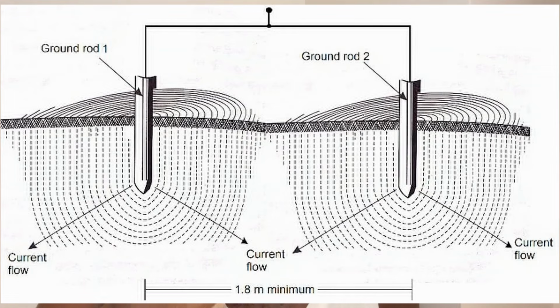Okay, if you're designing from scratch, I would say the earth rod should only be supplemental, bonded to the foundational earth itself, and installed in multiple locations if needed. Okay, if you didn't do the foundation earthing, that's not a problem, as long as you get the right quality of earth rod and you install them correctly, the right diameter, the right length, and spaced adequately, then you should be okay. But if you're starting from scratch, use the foundational earth system. It is much, much better. Never rely on a single earth rod for a modern house. It doesn't work. Common design mistakes.